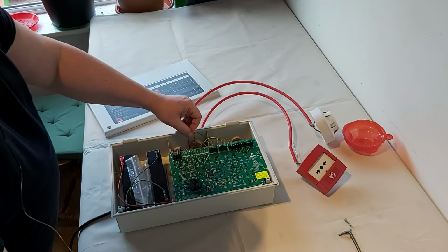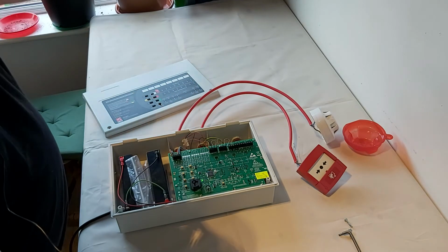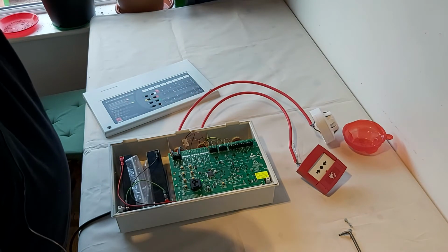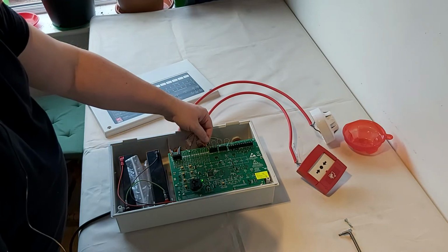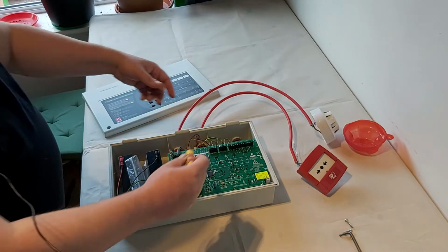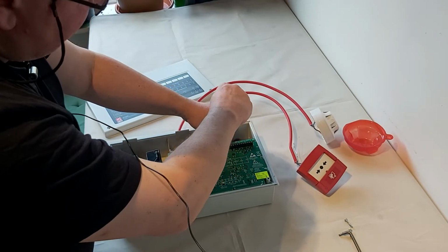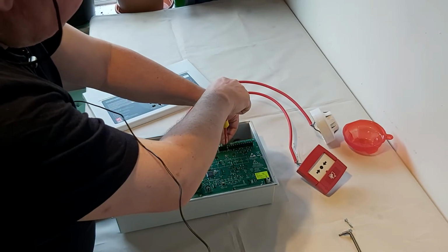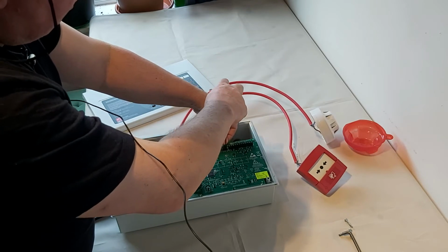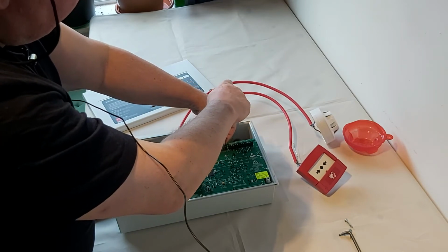So usually those cables would be regular fire cable, siren would be somewhere there, and end of the line device, in this case resistor, would be there. So if I disconnect one leg of this resistor on the fourth sounder line, it will start complaining.